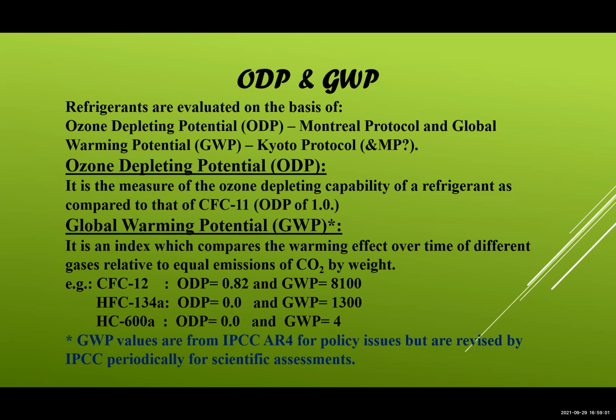Likewise, global warming potential for halocarbons, we used to quote halocarbon global warming potential. That was again with respect to R11, but now globally we define global warming potential with respect to carbon dioxide. So carbon dioxide global warming potential is 1. So I have given you some values: R12 is 8,100, R134a is 1,300, R600a is 4. So we talk about GWP. There are many refrigerants even today, what we are using, they have a fairly high GWP. And these values are taken from IPCC assessment report 4, although these values are being revised later, but for political purposes as well as policy purposes, we still use assessment report 4 values.